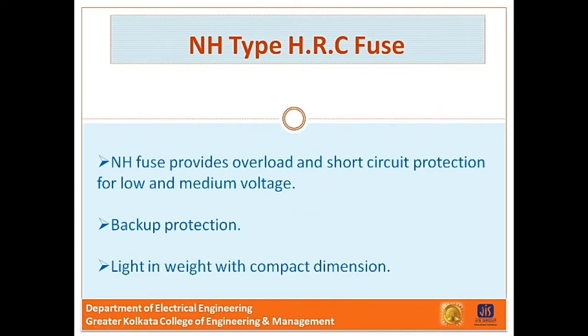First one is NH type HRC fuse. Now NH fuse provides overload and short circuit protection for low and medium voltage. They provide backup protection to a motor starter and other equipment against short circuit and overload. They are light in weight with compact dimension.